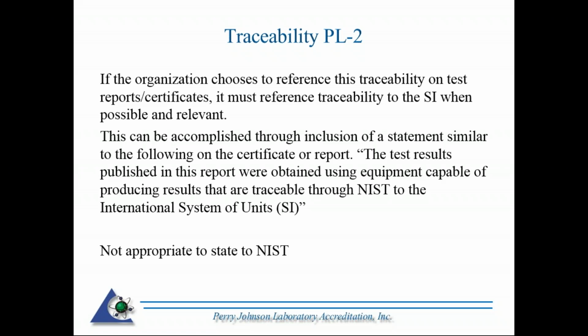Something else that's highlighted in PL2 is how to reference traceability. You used to see quite often "traceable to NIST," which is not appropriate. The folks at NIST do not like that. I've heard a speaker at NIST get quite animated about it when they see "traceable to NIST." You cannot state traceability directly to NIST. What I have here, taken right out of PL2, is an example. When you reference traceability, it's actually through NIST, through NIST to the SI. So the test results published in this report were obtained using equipment capable of producing results that are traceable through NIST to the International System of Units. So it's to the SI and is through the NMI.